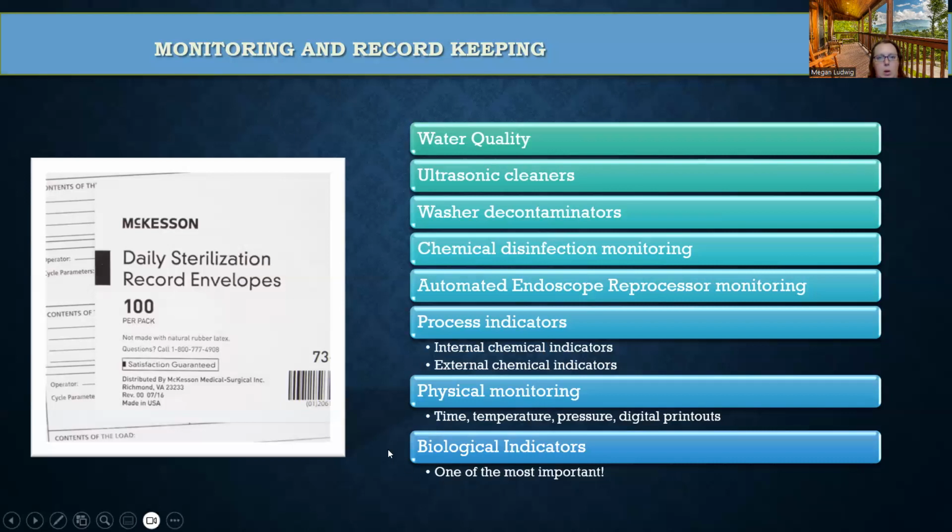Okay. And then the biological indicators for your sterilizer is the most important because remember, the biological indicator is the only one that can truly tell you if something was rendered sterile, not the chemical indicator, the biological. Because with the sterilizer, the biological indicator goes through its incubation period and is read after, which could be anywhere from 3 to 24 hours. And if that indicator came back with no spores growing, we know it's sterile.